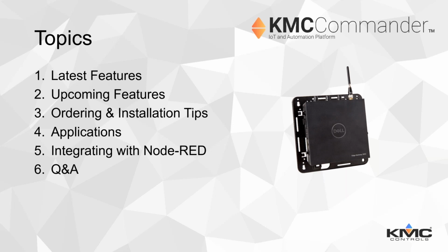Is there any reason why a certain project would only show a single VAV for an admin with all the topology checked, but another admin can view the entire project? My guess immediately from reading this is that the topology is independent of each user. It doesn't go over every user. I would double check the topology on that one user that's an admin. We've seen that a couple times. And if that doesn't answer your question, give us a call. Give Bear a call.